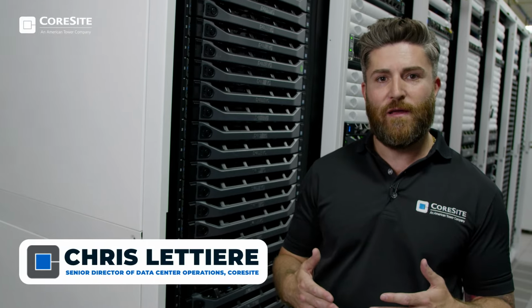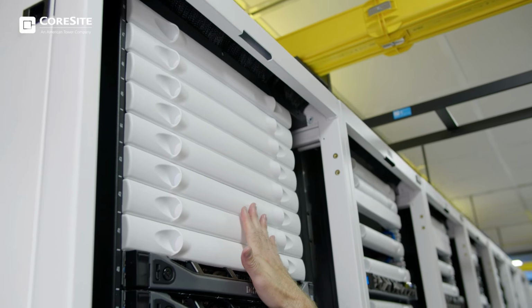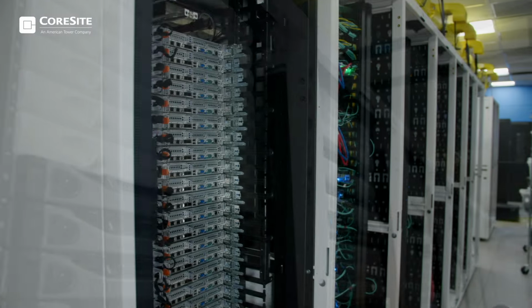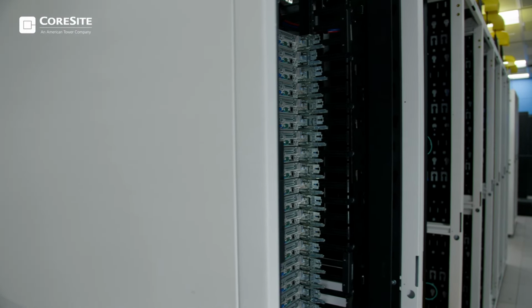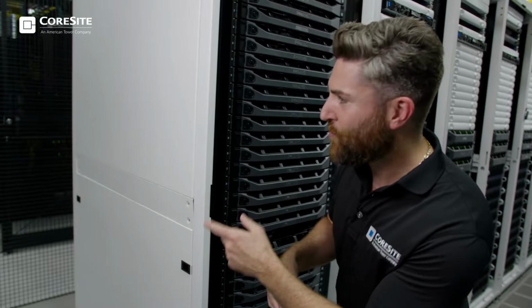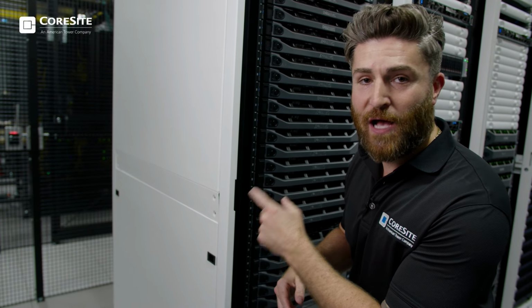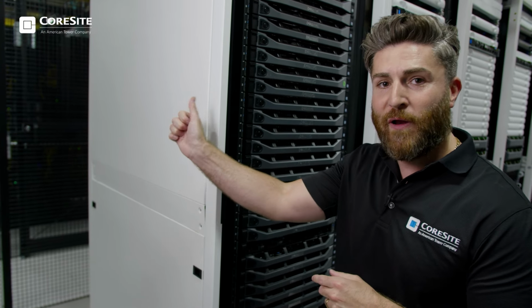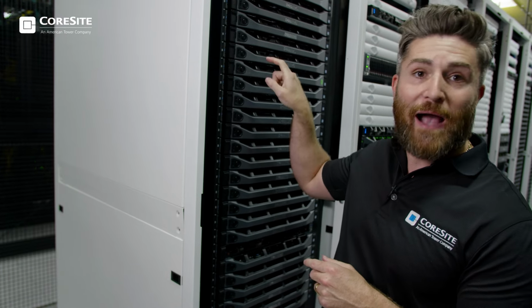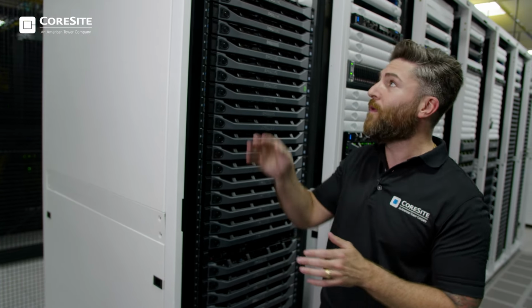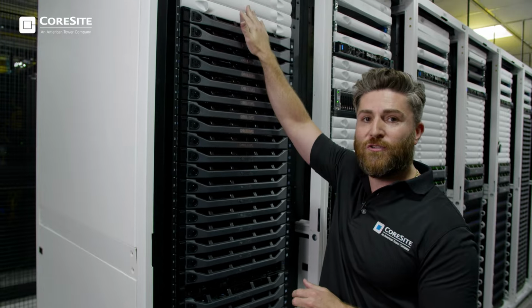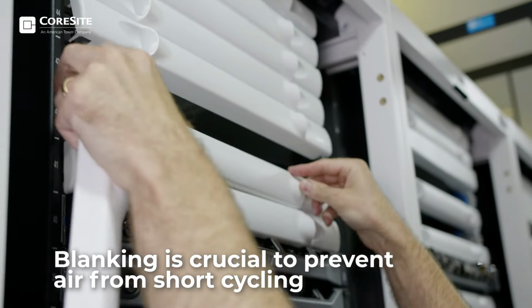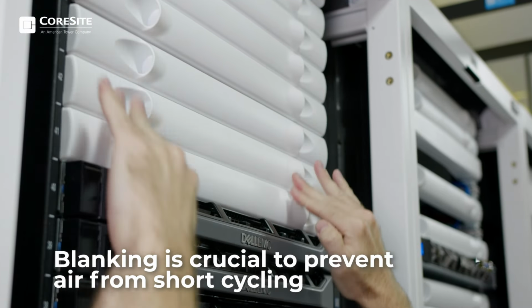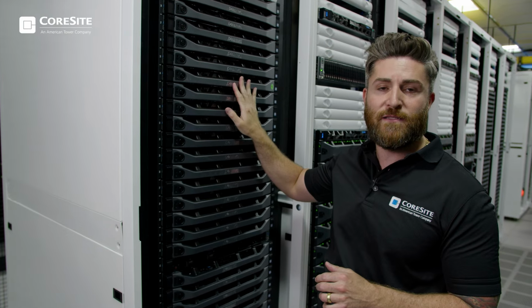Another way to achieve optimal efficiency in your data center is to ensure that blanking panels are installed in your cabinets and side panels are installed on end cabinets when appropriate. Just over there is the neighboring customer's hot aisle where their equipment is throwing hot air exhaust towards the back of this cabinet, which they share. If you don't have blanking panels installed, you could potentially be short cycling air from the hot aisle through the intake of the servers, causing heat issues inside your equipment.